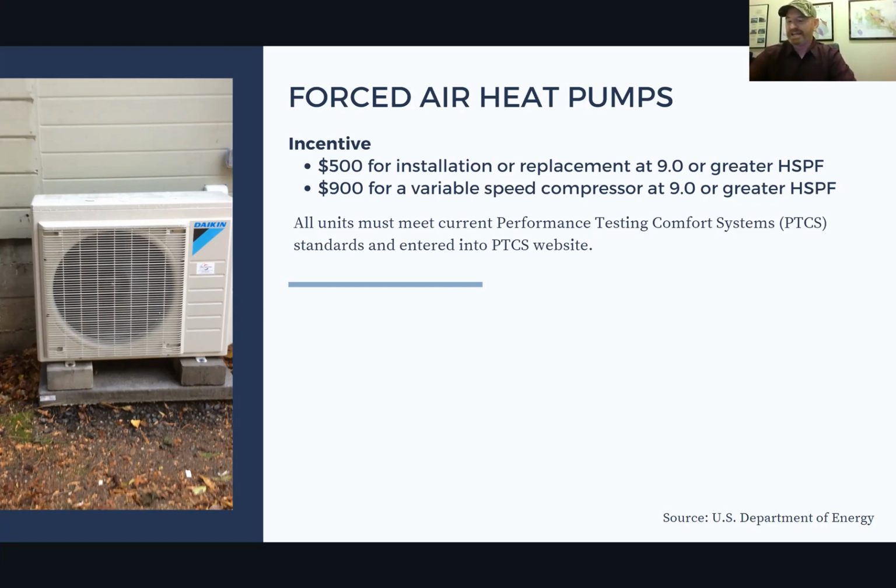And another way of controlling your energy bill, I should say, is with the heat pump, never move the thermostat more than 3 degrees at a time. I'm just talking in heat mode. So if you have a call temperature of 65 or 68 in the home and it's 65, that's fine, that's 3 degrees. But if you want it to go to 69 degrees, at more than 3 degrees, most heat pumps almost always bring on their auxiliary heater. And that auxiliary heater is almost always going to be electric resistance heat, the most expensive way to heat. So you can, next slide.